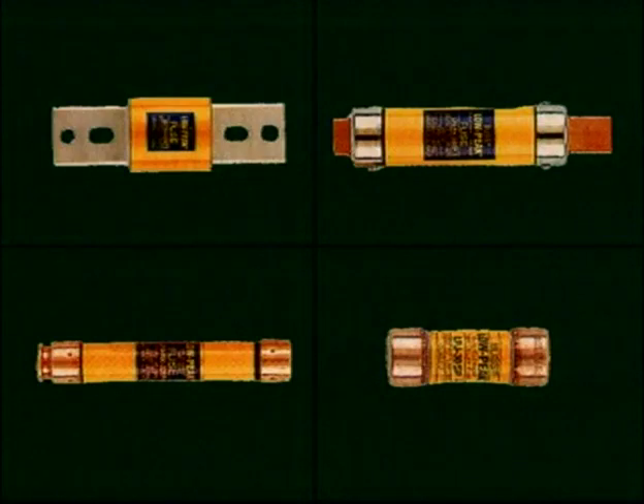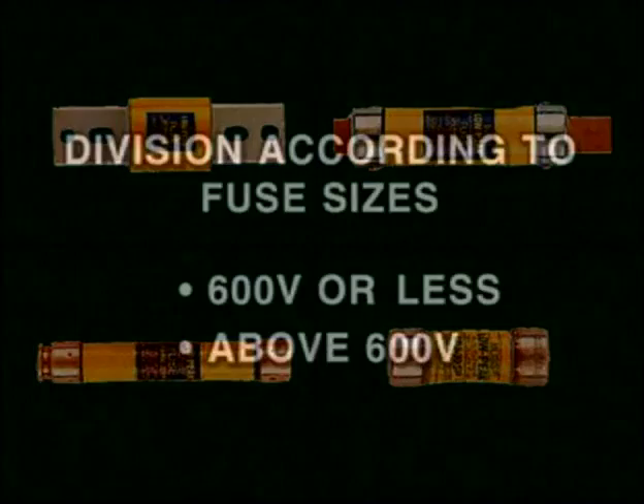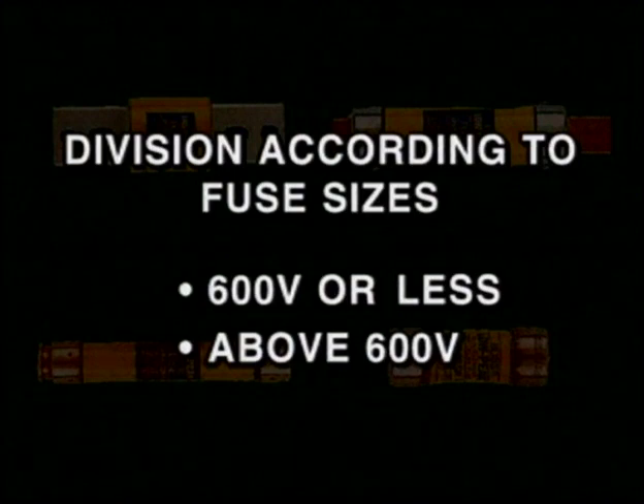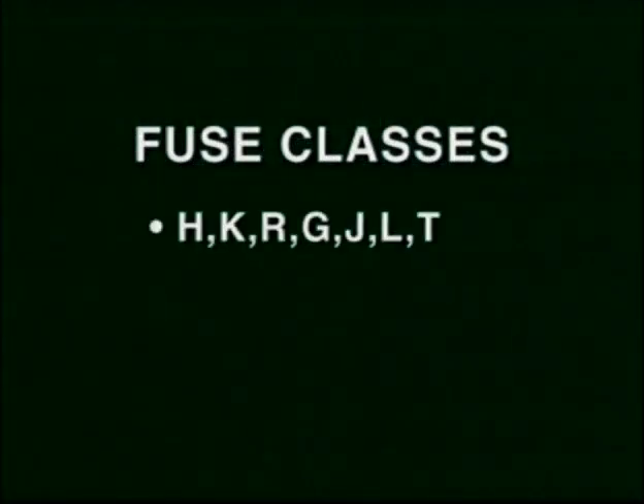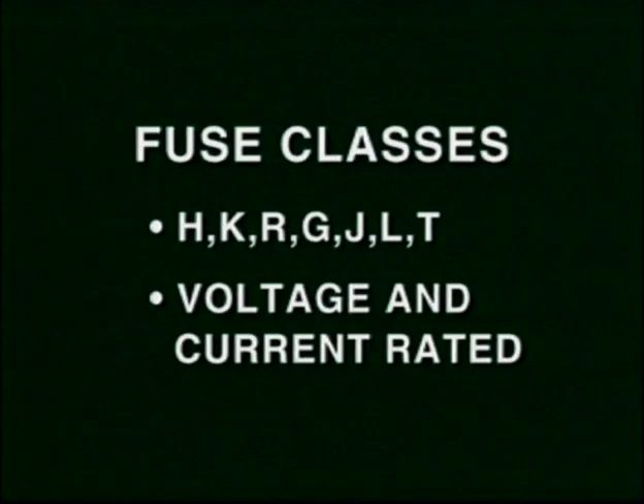There are several types of fuses available according to the base it mounts in, or the socket or adapter, as well as the interrupting current ratings. The basic division of fuse sizes is for 600 volts or less, and the other for voltages above 600 volts. Among fuses, there are also classes such as H, K, R, G, J, L, and T, which are rated for specific voltages and currents, depending on your application. These fuses will be placed in their respective holders. For example, these Class R rejection clips will accept only Class R type fuses.